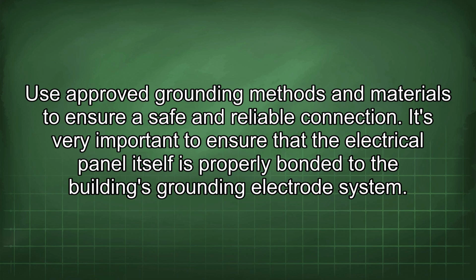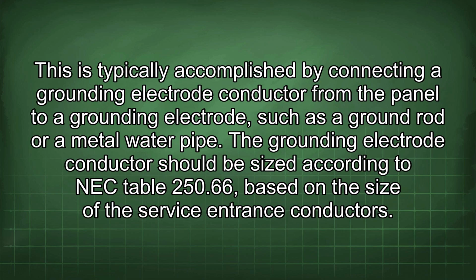It's very important to ensure that the electrical panel itself is properly bonded to the building's grounding electrode system. This is typically accomplished by connecting a grounding electrode conductor from the panel to a grounding electrode, such as a ground rod or a metal water pipe. The grounding electrode conductor should be sized according to NEC Table 250.66, based on the size of the service entrance conductors.